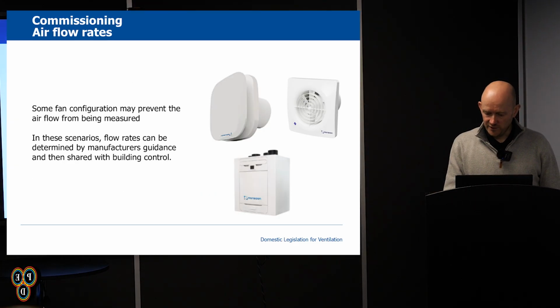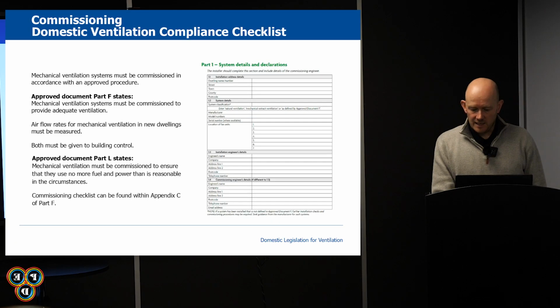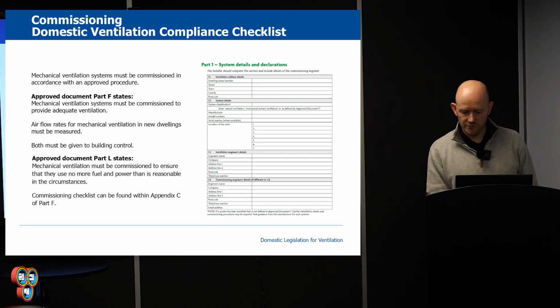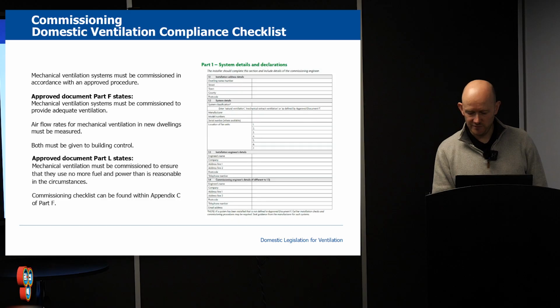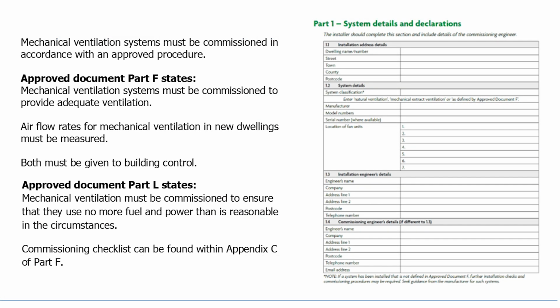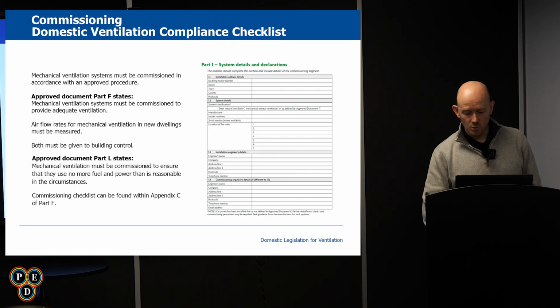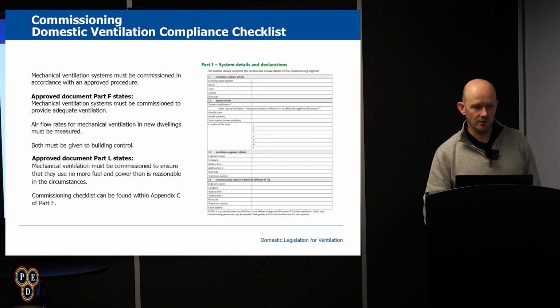In some scenarios, the configuration may prevent airflow from being measured. In these scenarios, you will need to determine the airflow rates as per manufacturer's guidelines. As per Part F, there is a compliance checklist that needs to be completed, which was previously part of the Domestic Ventilation and Commissioning Guide and can be found within Appendix C, and Part 1 is shown on the slide. Part 1 contains the particulars of the system, address of the installer. Part 2 is the installation checklist. Part 2B is a visual inspection or pre-commissioning checklist. Part 3 is for recording airflow measurements and from fans. All sections will need to be completed in order to demonstrate compliance.